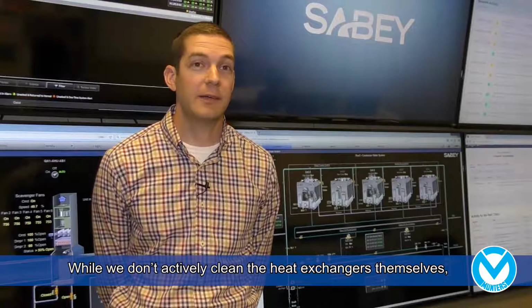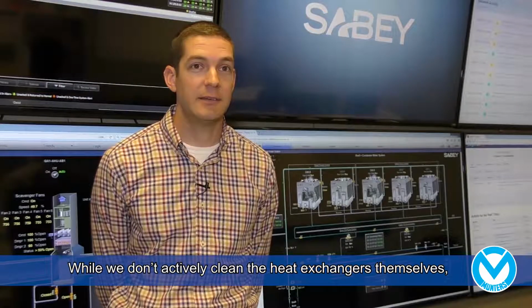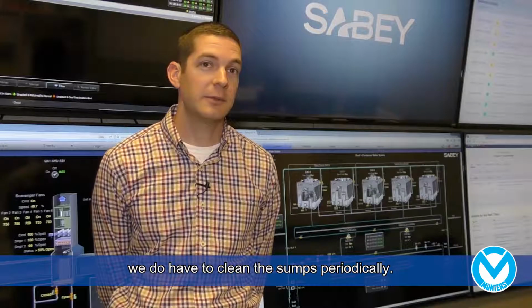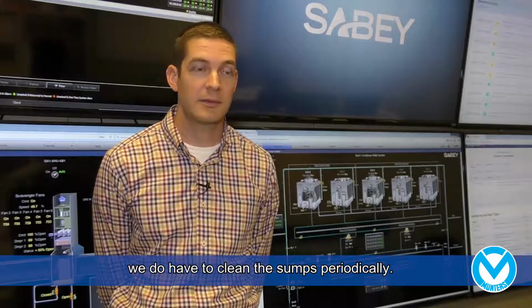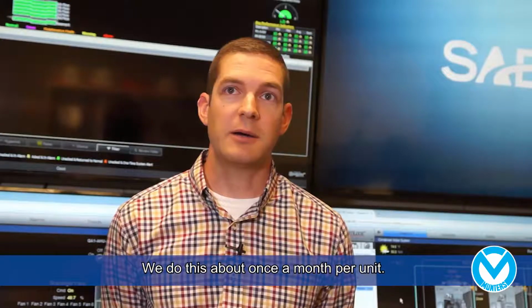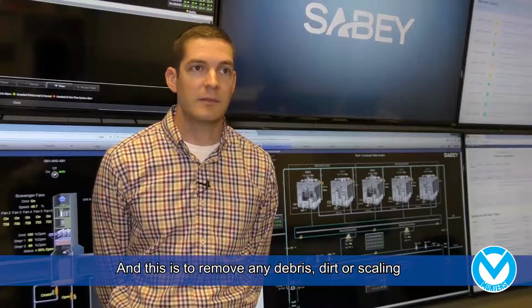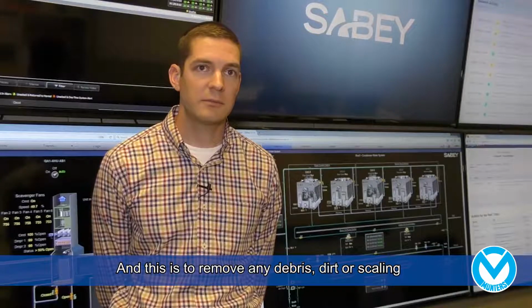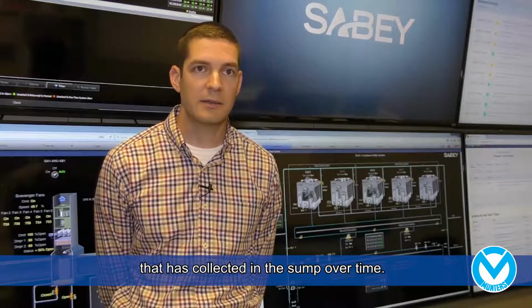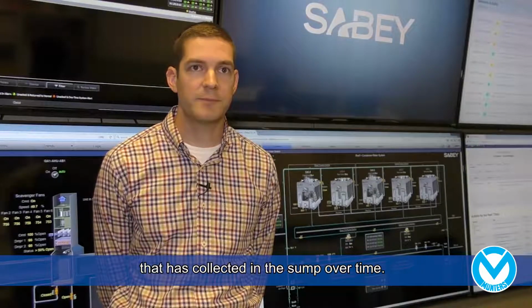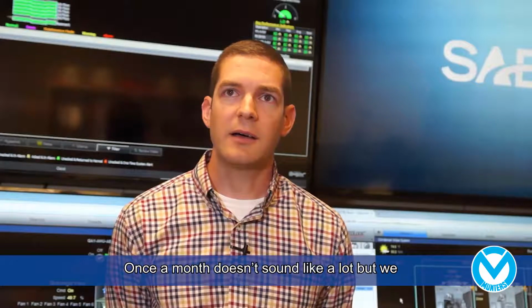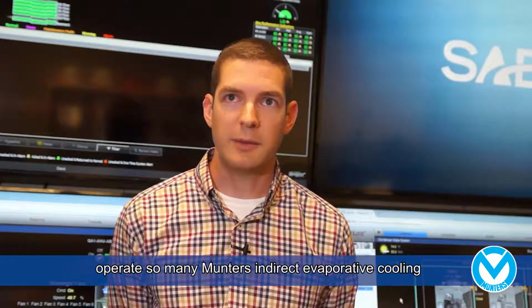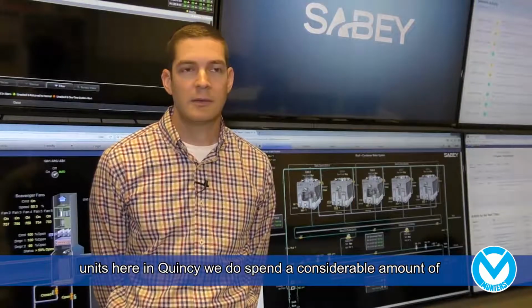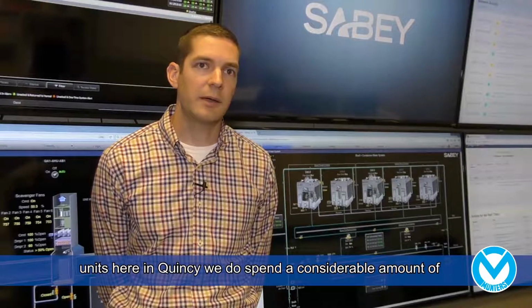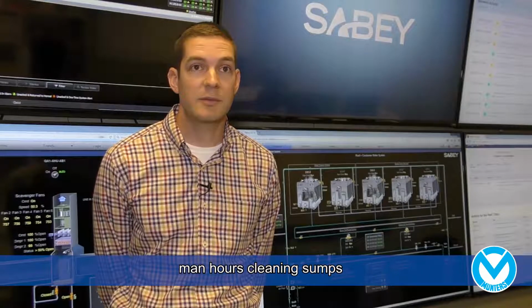While we don't have to actively clean the heat exchangers themselves, we do have to clean the sumps periodically. We do this about once a month per unit, and this is to remove any debris, dirt, or scaling that is collected in the sump over time. And once a month doesn't sound like a lot, but because we operate so many Munters indirect evaporative cooling units here in Quincy, we do spend a considerable amount of man-hours cleaning sumps.